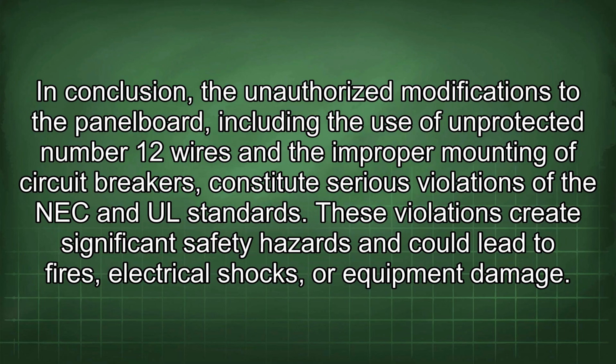In conclusion, the unauthorized modifications to the panel board, including the use of unprotected number 12 wires and the improper mounting of circuit breakers, constitute serious violations of the NEC and UL standards. These violations create significant safety hazards and could lead to fires, electrical shocks, or equipment damage.